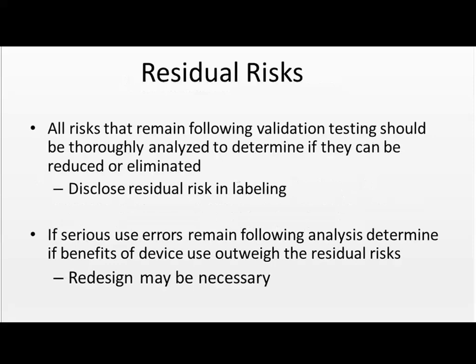Residual risks, very important subject for ISO and FDA. All risks that remain following validation testing should be thoroughly analyzed to determine if they can be reduced or eliminated.